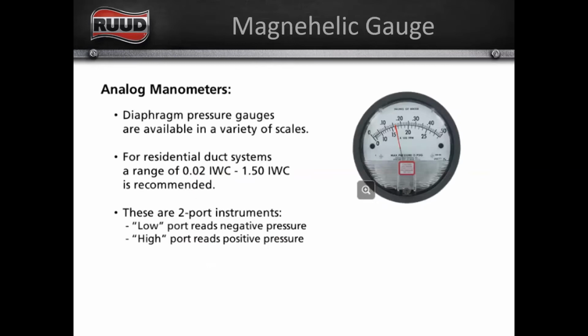So here is a magnehelic gauge, or a diagram of one. I think I said 2.5 inches water column earlier. I misspoke. We want to have a minimum of 1.5 inches. You can see the diagram here. This one only goes to 1/2 inch, and that's really not enough to measure most duct systems. A 1.5 inch water column would be ideal.